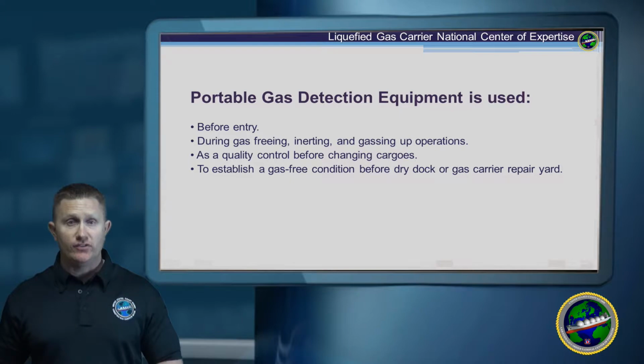The ship's crew needs the ability to test the atmosphere in enclosed spaces for O2, toxic gases, hydrocarbons, and flammable vapors. They normally do this before entry into enclosed spaces, during gas freeing, inerting, and gassing up operations, as a quality control measure before changing cargoes, and to establish a gas-free condition before dry dock or before the gas carrier goes to the shipyard.